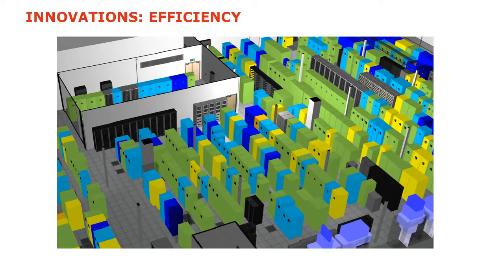So what this is showing is the temperature of those individual cabinets, whether they're happy, whether they're unhappy. Dark blue probably means it's being slightly overcooled, so we're wasting a bit of energy by putting too much cooling in there. Green is optimal. We get into yellow and orange and even red, that will show that the cooling within that particular cabinet and equipment is actually not sufficient, and therefore we need to change what we're doing and the way we're doing it.